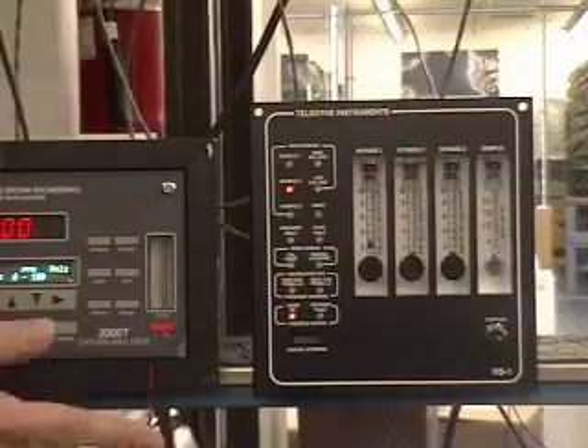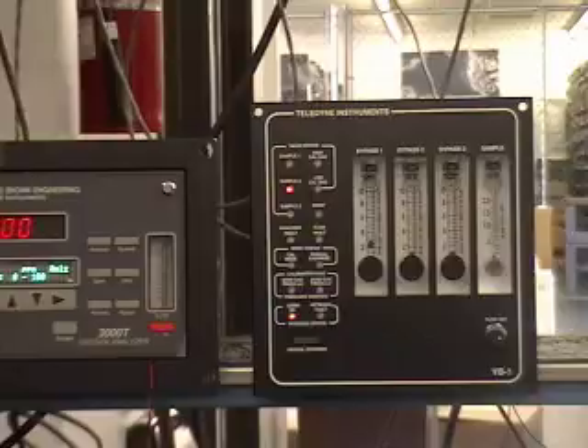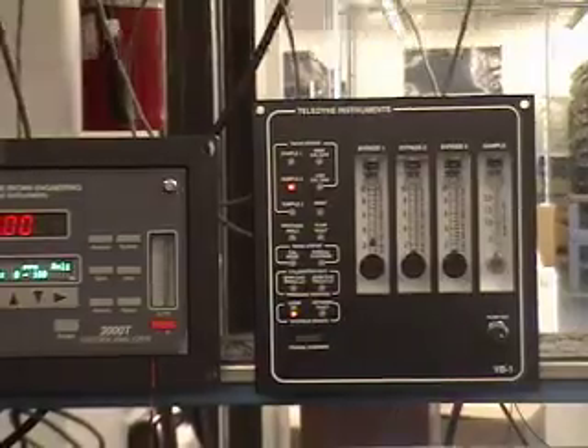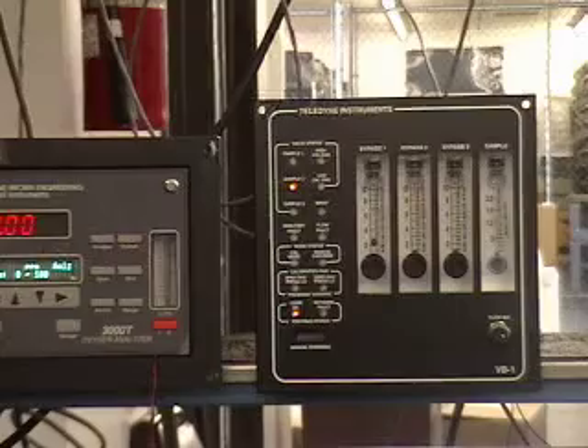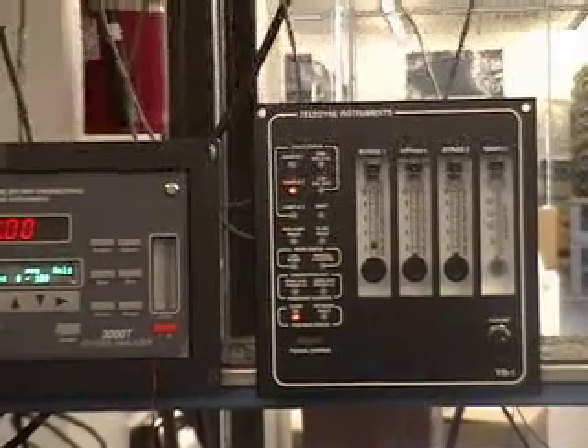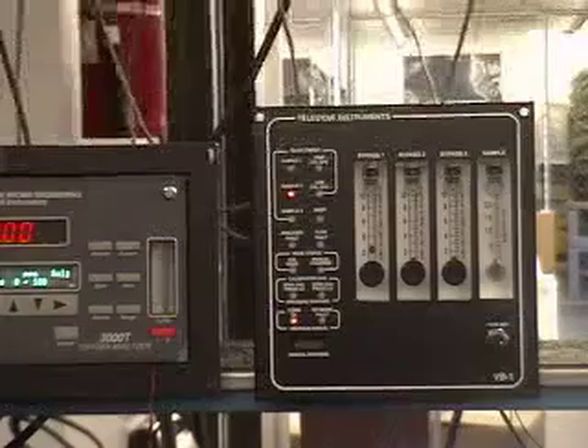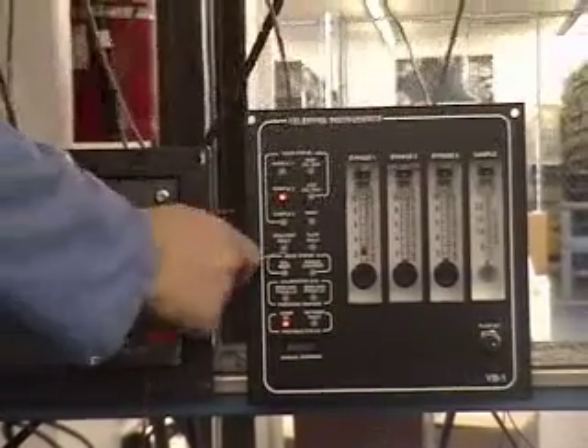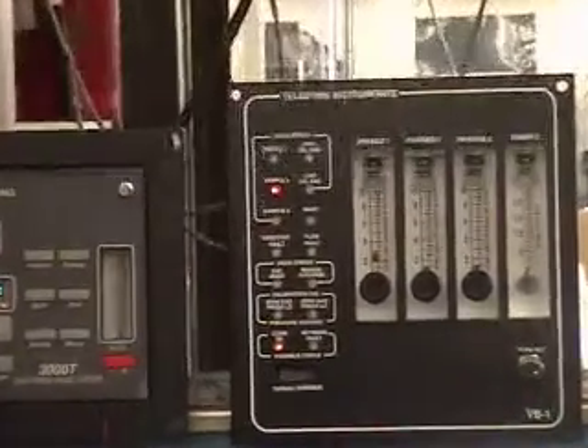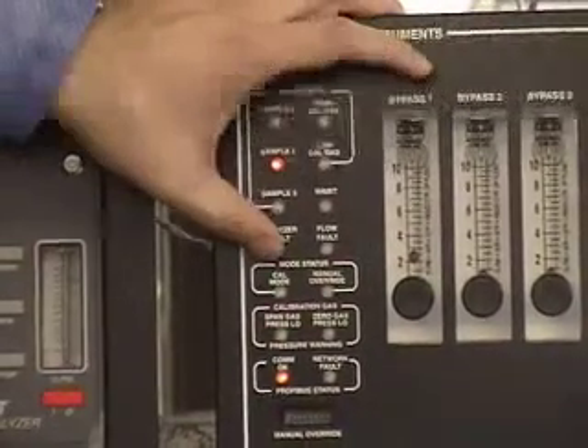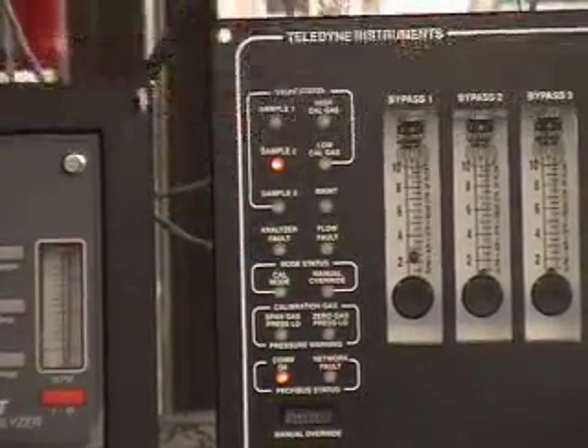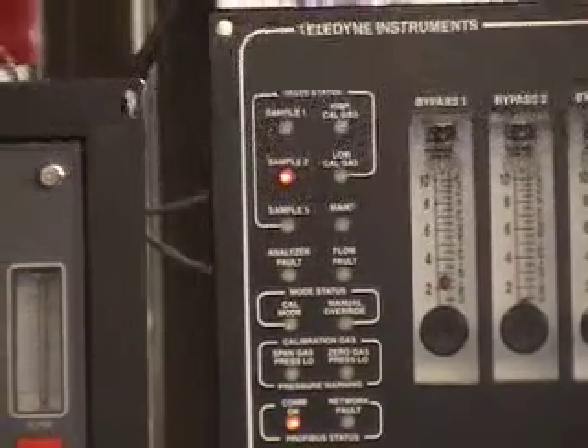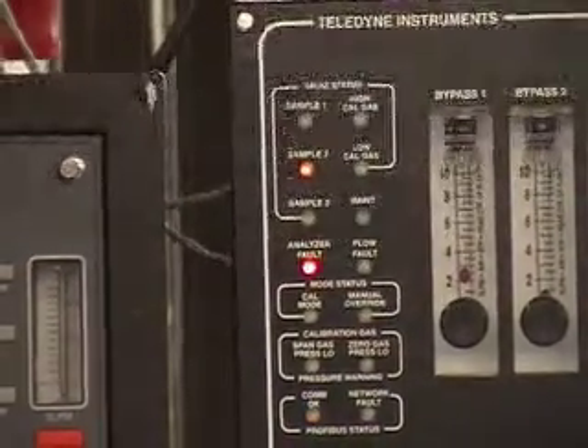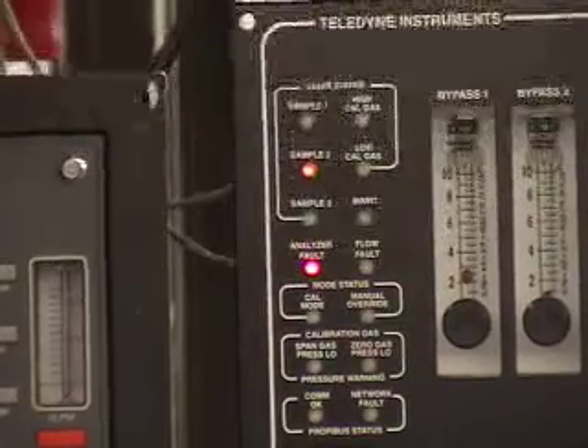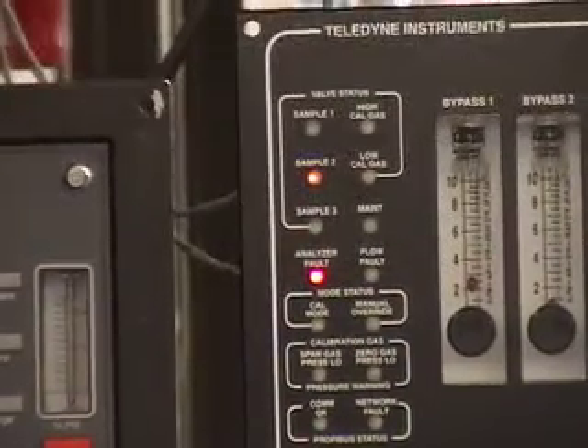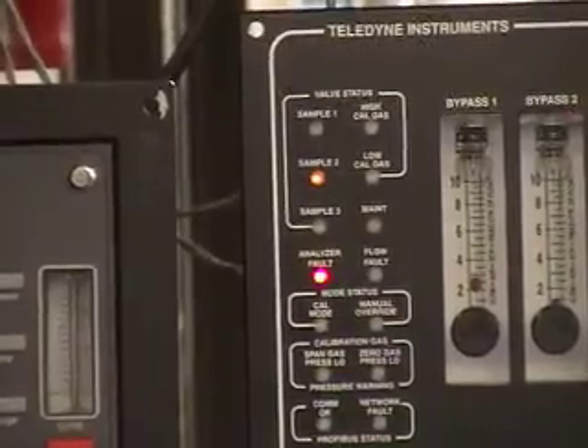Okay, so we did all the functions of the analyzer here right now, using the Profibus network. Now, we will exercise a few other things before we move on to other modes. We've got an analyzer fault light. That means if for some reason we lose communication on the RS-232, the analyzer fault light will come on. So I'm going to disconnect the RS-232 for a moment. I disconnected the RS-232 and the analyzer fault light came on. So it means something is wrong with the analyzer, we lost communication with it. Go and check it out.